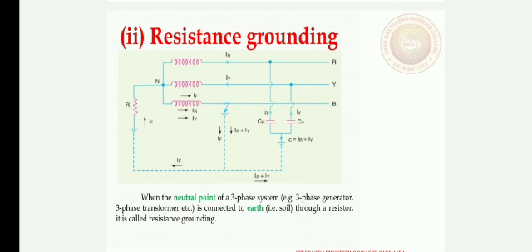Second one, resistance grounding. When the neutral point of a three-phase system is connected to earth through a resistor, it is called resistance grounding. The resistor may be either of wire or water column resistances for voltages of 6.6 kV and above. This method is normally adopted in systems with voltages from 2.2 kV to 33 kV with a power source capacity of more than 5000 kVA.